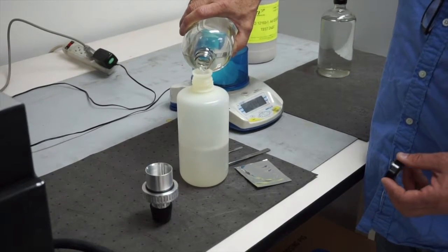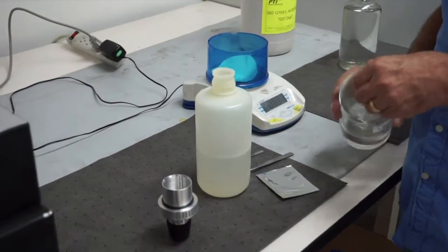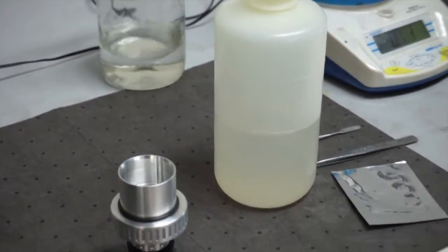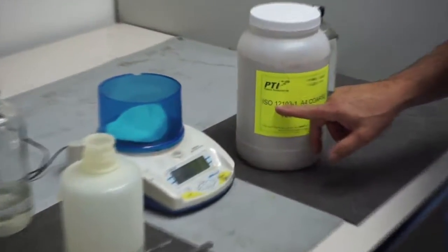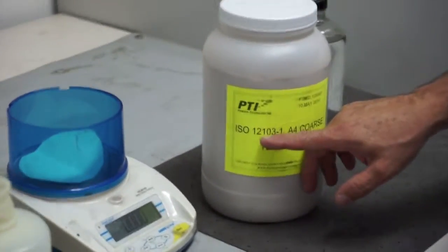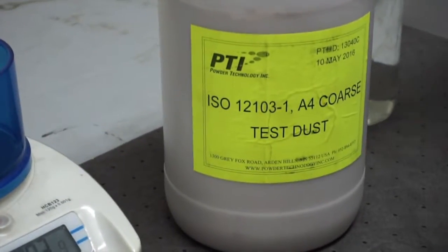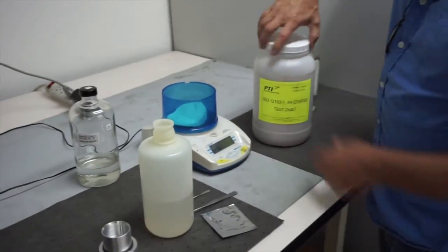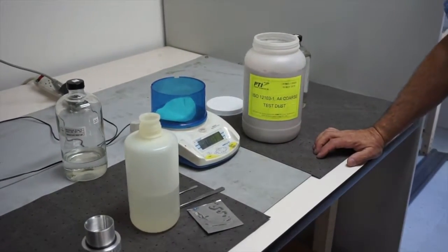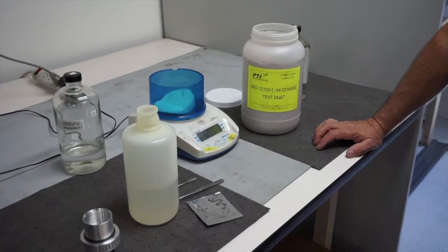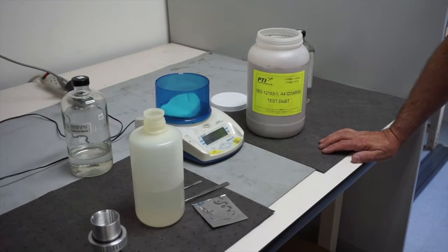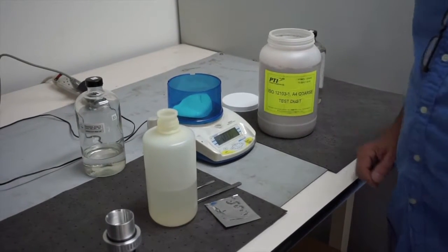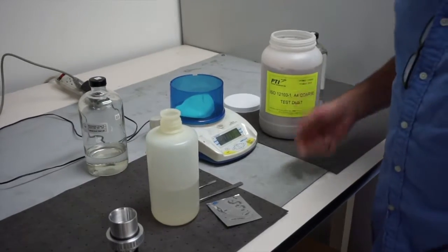So basically we just measure in 500 milliliters of fuel, and for particulate today we're using an ISO 12103-1 A4 coarse test dust, which is a standard that's pretty widely used in the industry. And the range of the measurement is 0 to 15 milligrams per liter. So since we have 500 milliliters of fuel, we can really only put in about seven milligrams of test dust, which is a very small amount.